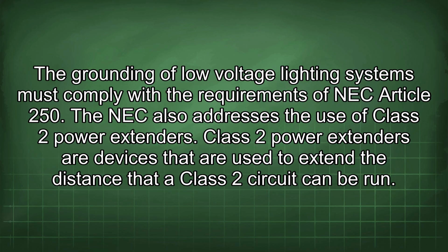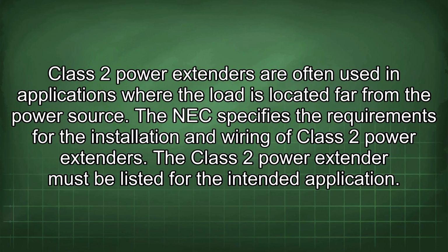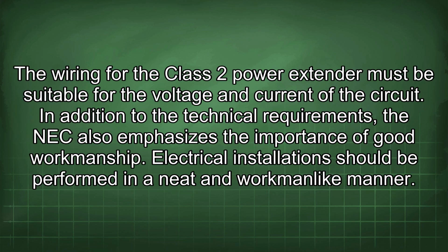The NEC also addresses the use of Class 2 power extenders. Class 2 power extenders are devices that are used to extend the distance that a Class 2 circuit can be run. Class 2 power extenders are often used in applications where the load is located far from the power source. The NEC specifies the requirements for the installation and wiring of Class 2 power extenders. The Class 2 power extender must be listed for the intended application. The wiring for the Class 2 power extender must be suitable for the voltage and current of the circuit.